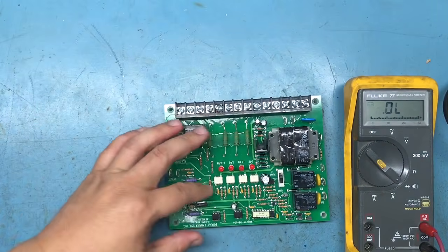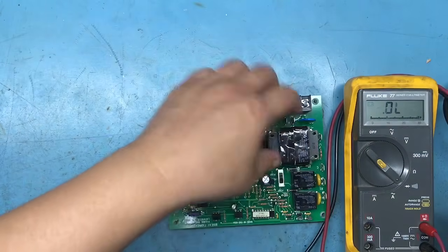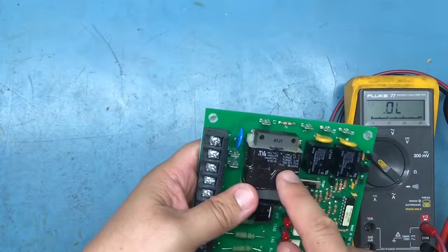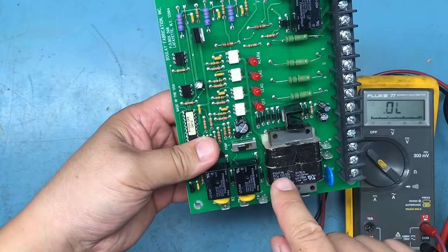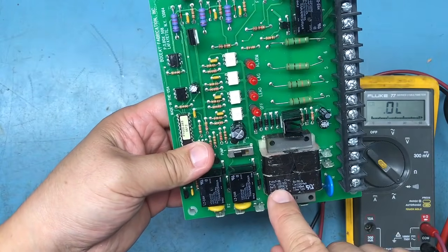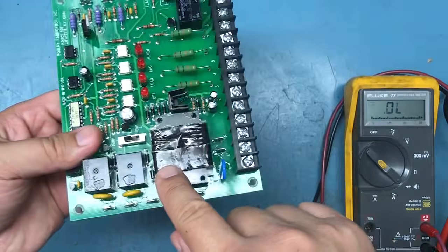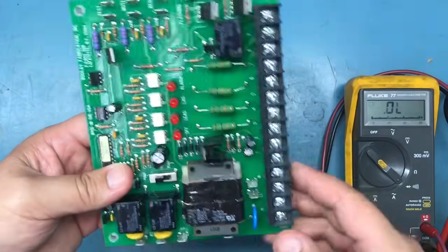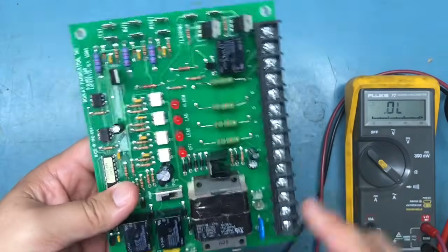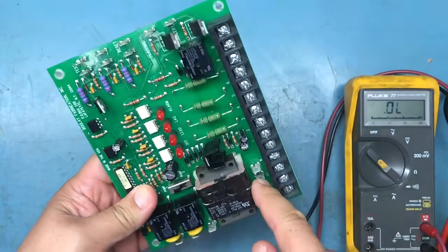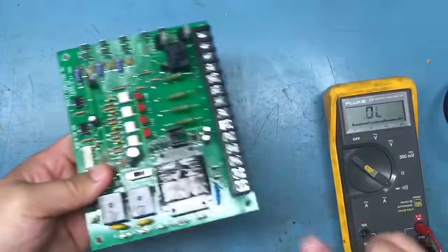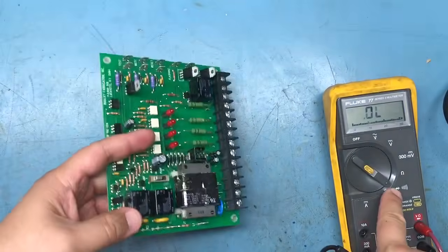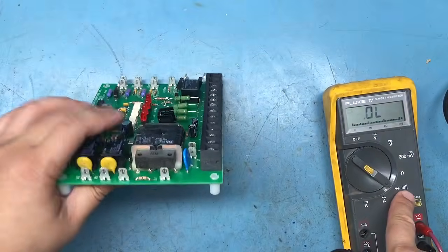I mean, I could test these optos too, but let's say I want to power this up. I'm looking at this transformer and I know how a transformer works. On here it says 115 on primary, and then on secondary I'm going to get 23 volts AC. I don't know if you guys can see that. And then I'm going to say, okay, where's my input? Well, just by looking here, I can see an L1 and my neutral. So I'll leave it on my diode setting, which is going to be my continuity.